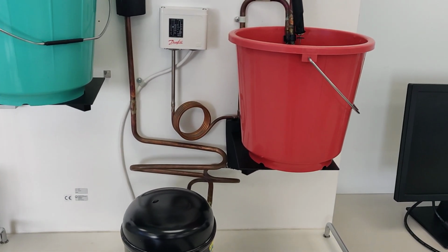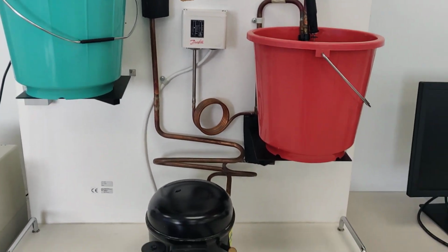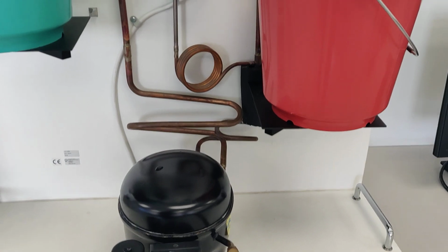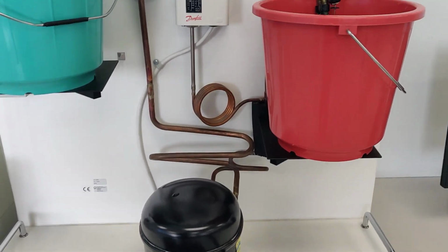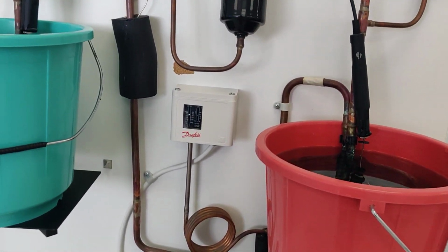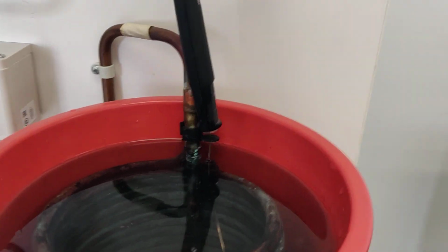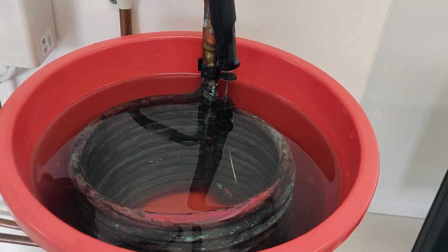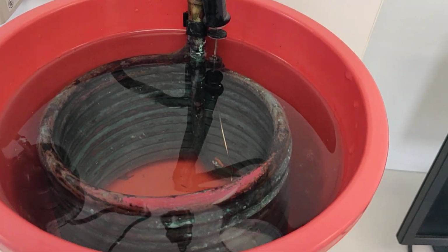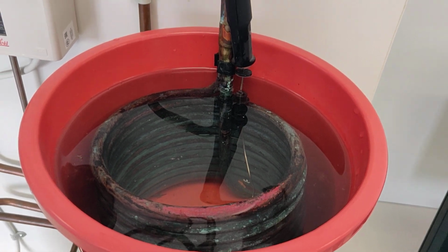Freon, or more specifically it is refrigerant 134A, that is used with this setup here. So refrigerant 134A enters the compressor, gets compressed to high temperature, high pressure, and the high temperature, high pressure refrigerant travels through these tubes and moves in this coil. And since it is hot, it will heat the surrounding fluid. Hence the name of this coil is heating coil.